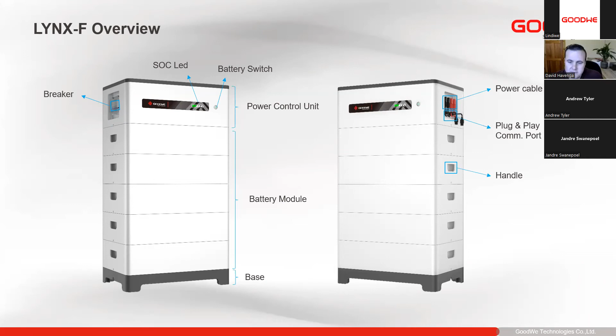As you'll see, the system weight on this is 105 to 235 kilograms. Each cell is roughly 40 to 50 kilograms, along with the BMS and the bottom plate together. The minimum size is 2 cells, along with the BMS and the floor plate, which gives you a minimum of 105 kilograms. These are IP55 rated batteries. The operating temperature is 0 to 50 degrees Celsius. They can discharge down to minus 20 degrees Celsius. Because of the higher voltage, they do give us a wider range.